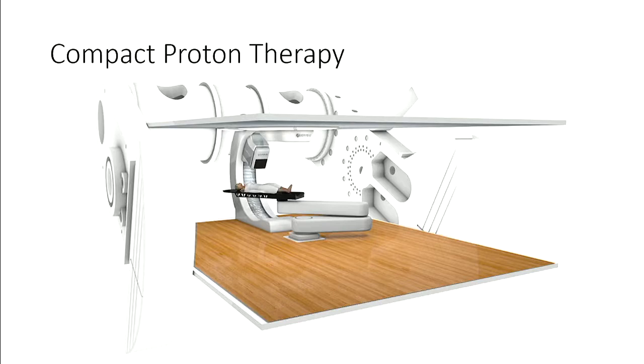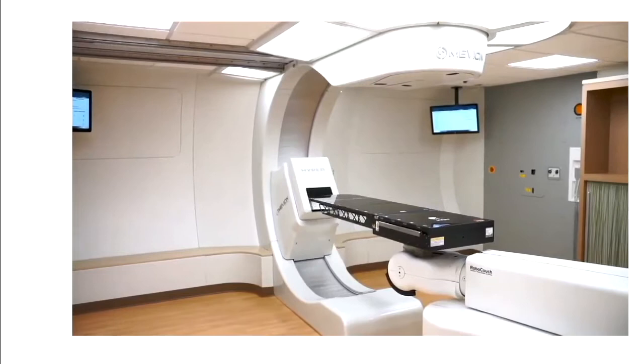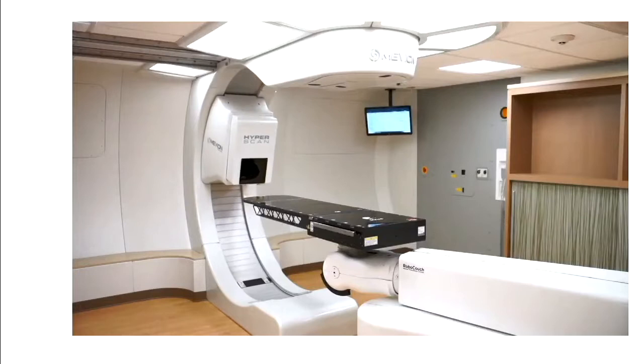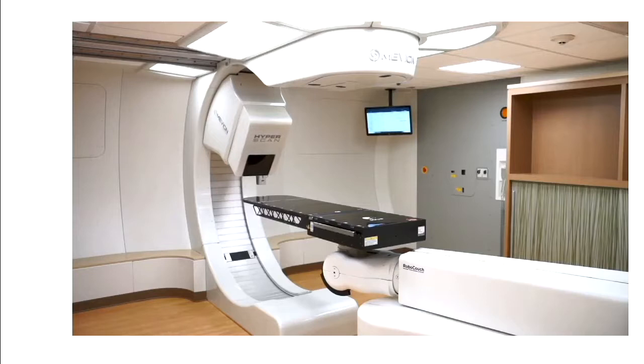The patient is two meters away from the exit of the accelerator. Everything we do to shape the beam has to happen in between that exit and the patient. The structure is the gantry with counterweights to counterbalance the accelerator. The whole facility fits in a 30-foot cube — sort of a three-story building. Here's what the treatment room looks like: there's the robotic couch and the nozzle, and behind the wall you see the accelerator rotating through — in this case 190 degrees — which the patient would never see but is right behind the wall.